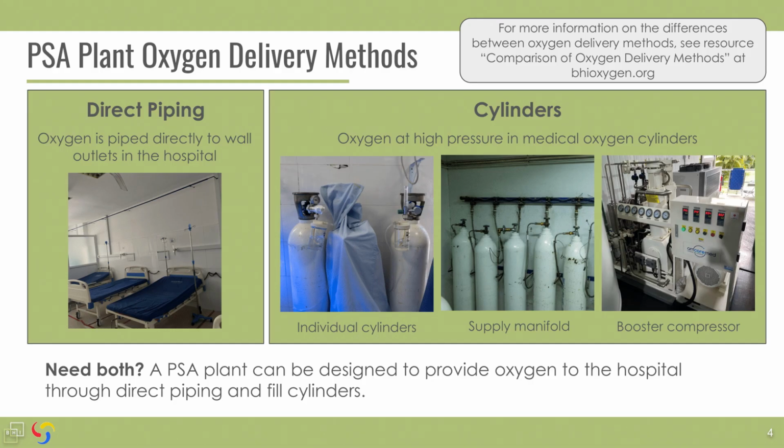Booster compressors. Whether oxygen cylinders will be used individually or in a supply manifold, extra equipment will be needed in the PSA plant. Cylinder filling compressors, often called booster compressors, are the systems that fill cylinders at high pressure.